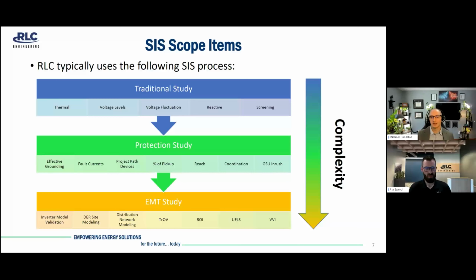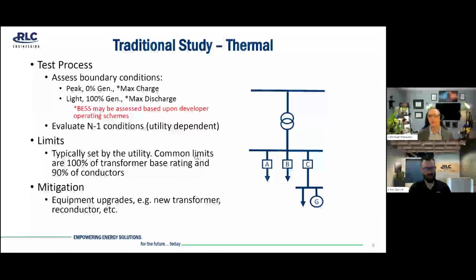So with that, let's dive into the traditional study elements here and look at thermal. So the test process for a thermal evaluation is to typically look at the boundary conditions. We look at a snapshot of peak loading, 0% generation. And if you have batteries on the system, we would also look at a maximum charging scenario potentially. The other snapshot that we typically look at to kind of bookend this is the maximum export scenario, which would be a light load, 100% generation, and max discharge if there are any batteries.